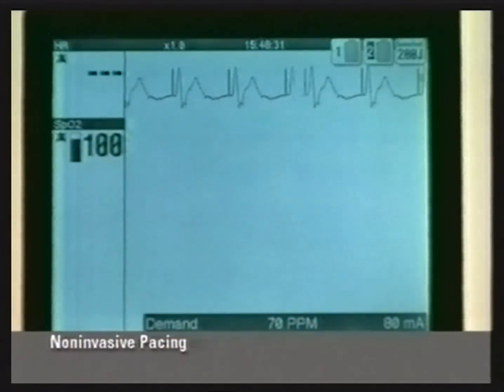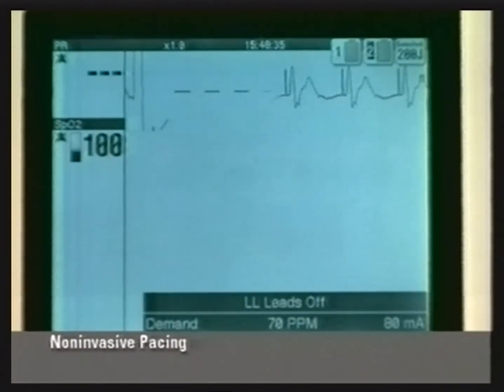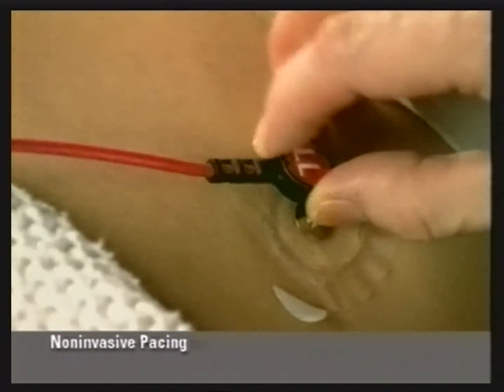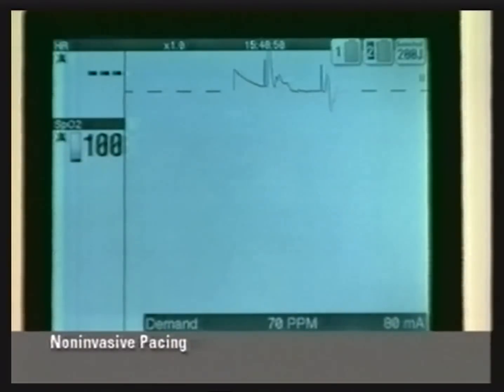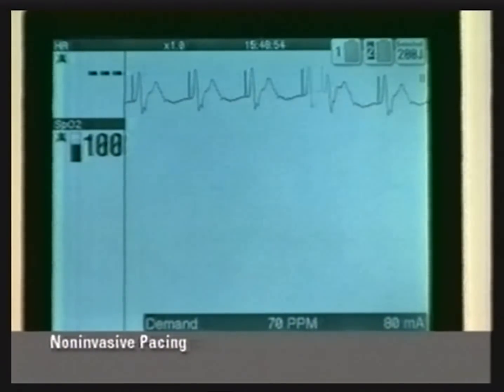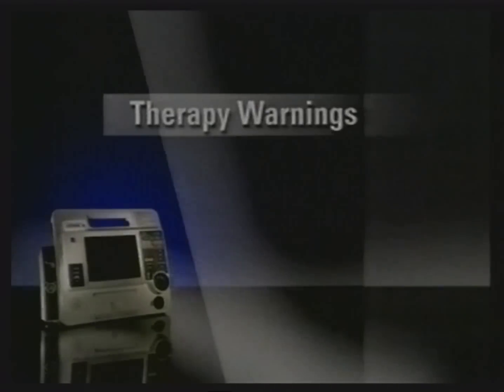If the monitor detects an ECG lead-off condition during pacing, the ECG trace becomes a dashed line and an alert tone sounds. Pacing therapy continues as a status message indicates, but at a fixed rate, regardless of the patient's own rate. Replacing the ECG lead restores the trace and clears the alarm. This concludes the non-invasive pacing section of this video.